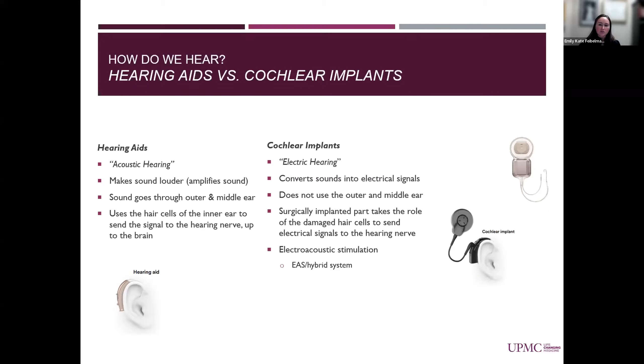There are two main styles of cochlear implant processors. There's the behind the ear style, which sits on the ear like a hearing aid, but there is an extra piece that sits up and back behind the ear to connect to the internal device that's surgically placed. And then there is the off the ear processor, which works the exact same way, except everything is contained in the one smaller piece that sits right on that magnet site.